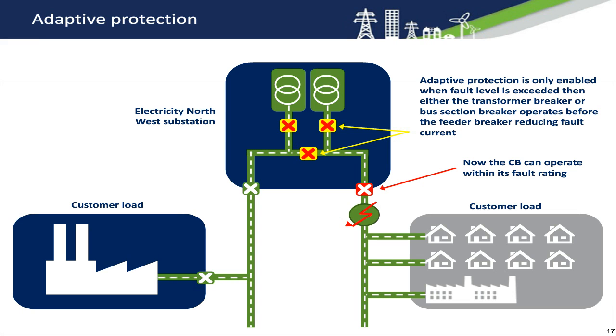In this example, the red circuit breaker would not normally operate first, removing the fault from the network. However, in this example, the red circuit breaker's fault level has been exceeded. So the fault level assessment tool could enable any other circuit breakers in yellow, so they will open quicker than the red circuit breaker, reducing the fault level on the network, so the red circuit breaker can operate safely beneath its fault rating. We have this technique successfully installed and working at 5 of our substations, and so far we have had 3 successful operations of adaptive protection.